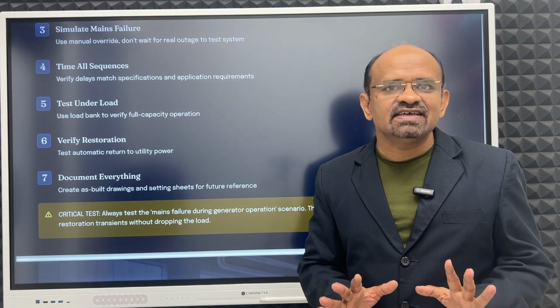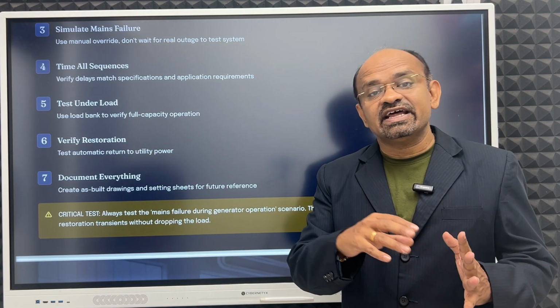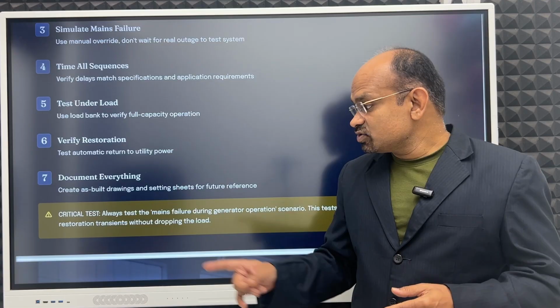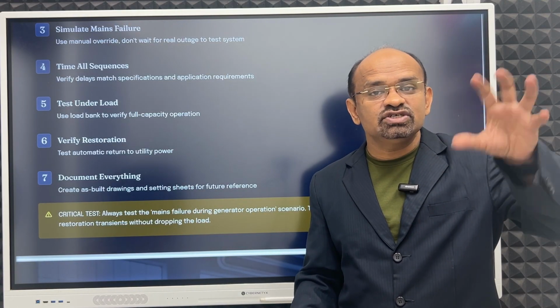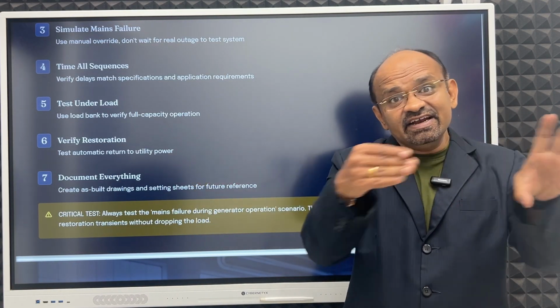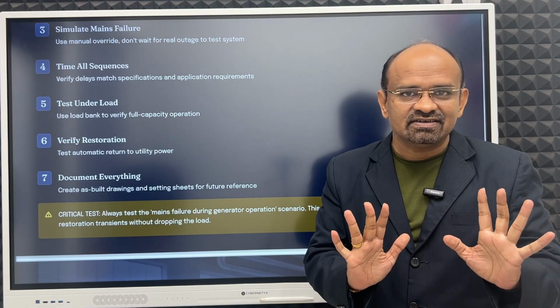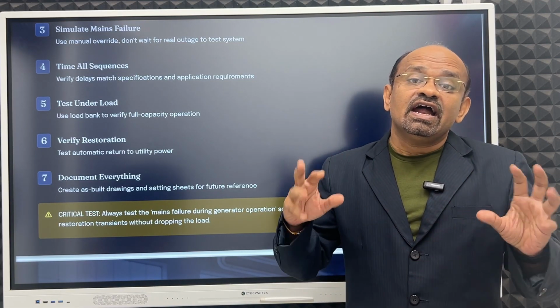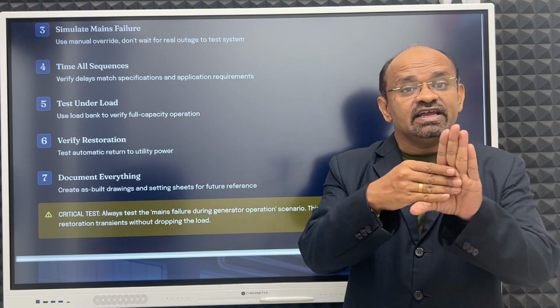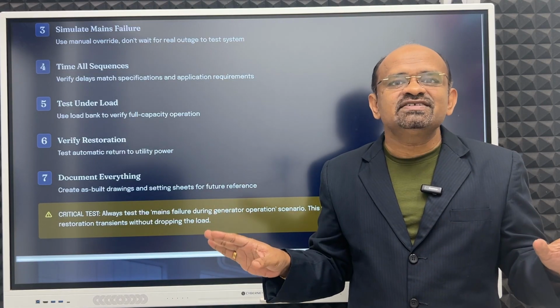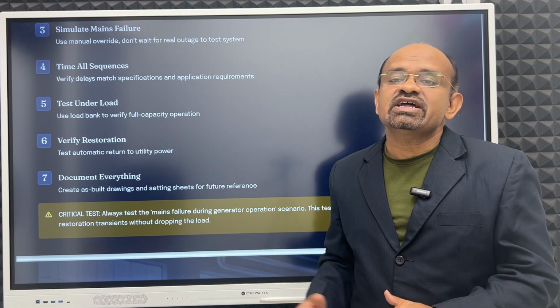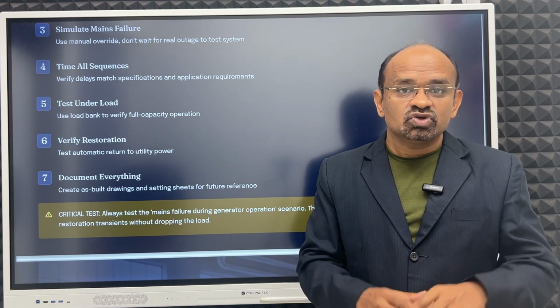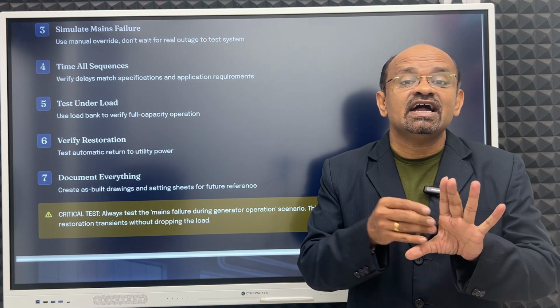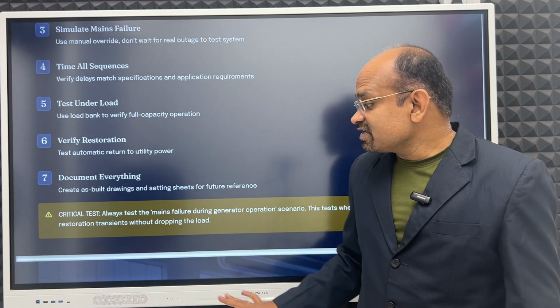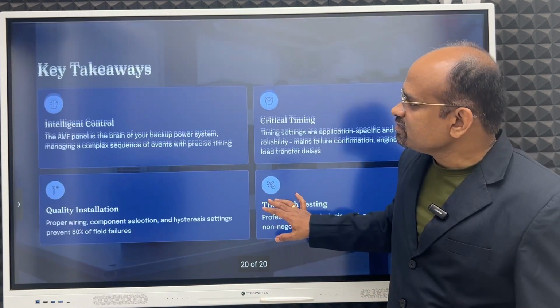For that, delay is there. It will not put the load directly on the DG. So this is very important. The DG should be working, and it should sustain that inrush. Otherwise, at the time of emergency, the inrush will damage our system and we will not have the emergency backup. So it should sustain that inrush current or transient.